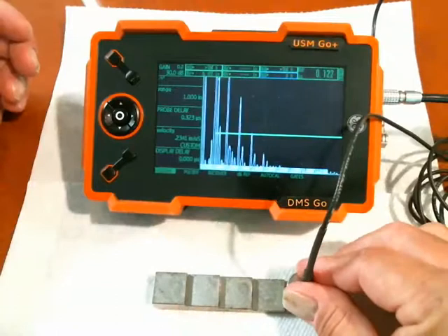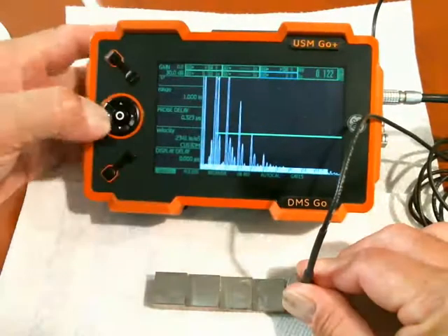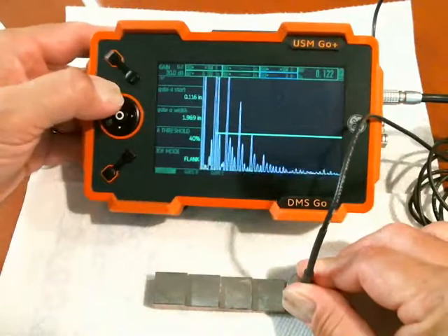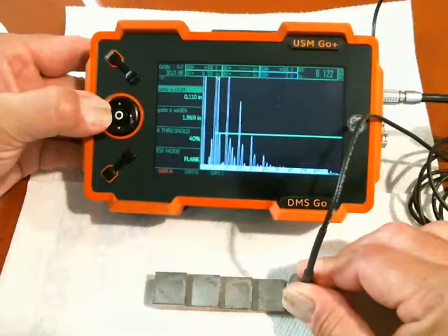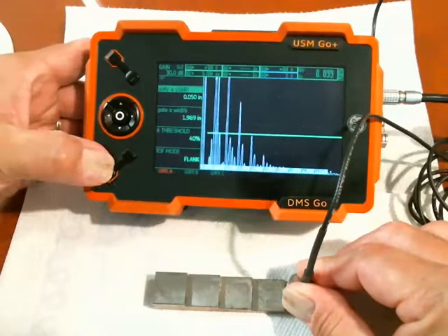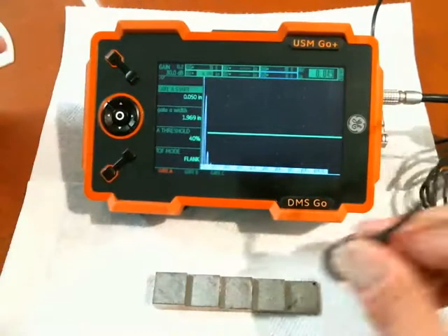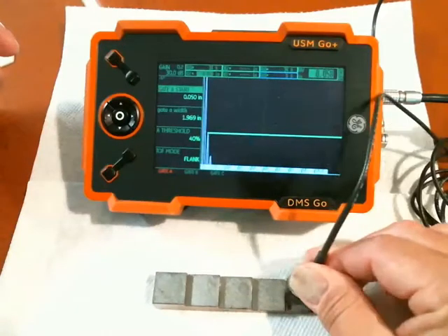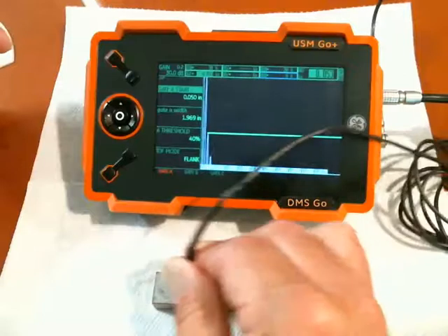If I go down to the 0.1 step, I notice I'm off a little bit. That's because my gate is starting too late. So I may have to go to my A gate and move the gate start in a little bit — just want to make sure it stays out of the ring-down from the initial pulse. There's my start: 0.1 inch, 0.2, 0.4, 0.5.